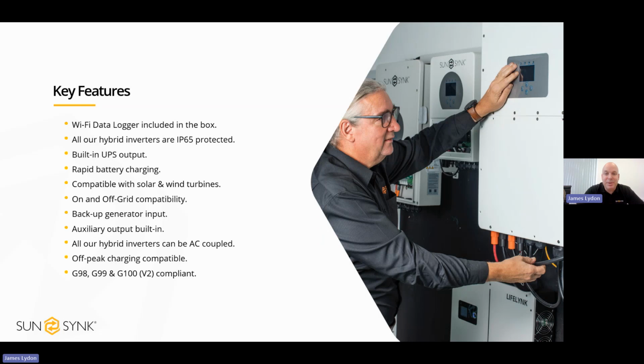Next one, all of our hybrid inverters can be AC coupled. So if you've got a customer, whether it's domestic or commercial, and they've got an existing grid-tied system on site, you can leave that grid-tied system there. You don't need to remove it. So, especially for commercial sites, if you've got a commercial building with 500 kilowatt of PV, they might be running that on, let's say, 500 kilowatt grid-tied inverters. What you can do with our system is grid connect our system, have your batteries connected to it, and our smart CT will see when those other systems are exporting to the grid. And as soon as our CT sees that export, it will automatically divert it into the batteries.